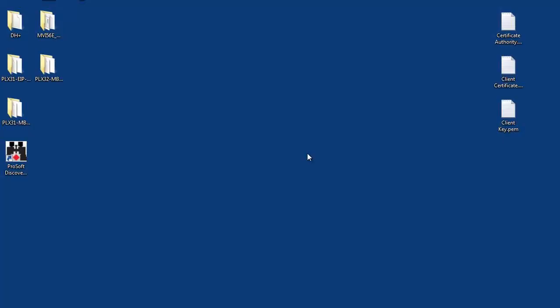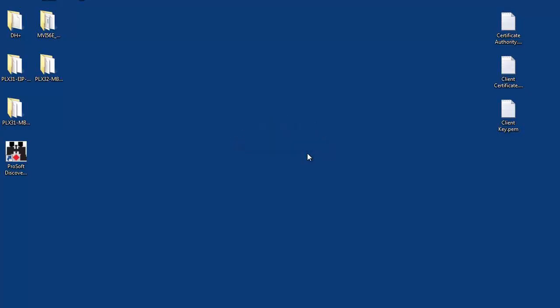When you receive the radio it comes with the default IP address of 192.168.0.250. In order to configure the radio we need to have access to that web page. You can set the IP address of your computer to match the subnet of the ICX-35's default IP or you can change the IP address of the cell modem using our ProSoft Discovery service. This is a free utility that you can download from our web page.